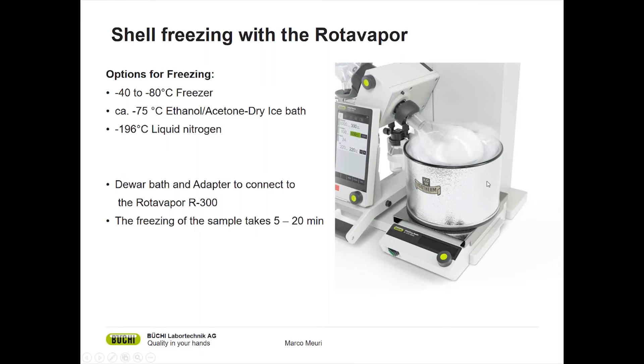What we recommend if you work with manifolds and round bottom flasks is that you use a cooling bath, as you can see in the picture, with dry ice and ethanol or acetone, and you use a rotary evaporator R300 and rotate the flask. You can attach your sample, dip the flask into the cooling bath and start the rotation. It will take about 5 to 20 minutes depending on your sample and the amount until your sample is completely frozen and can be attached to the freeze dryer.